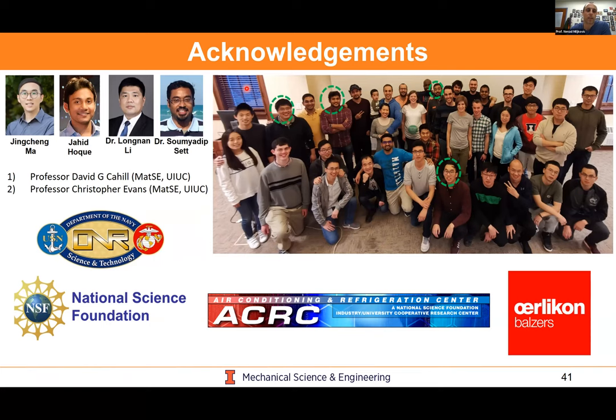Can these be used inside heat pipes without issues of non-condensable gas generation? These are very thin formulations that are very stable—covalent bonds. Non-condensable gases are very important; even 5 parts per million can ruin heat transfer performance. But for the surfaces and timescales we've used, we haven't seen any outgassing, swelling, or similar problems, especially for fluorinated diamond-like carbon, which has really hard covalent bonding and is very stable. Hopefully that answers it.